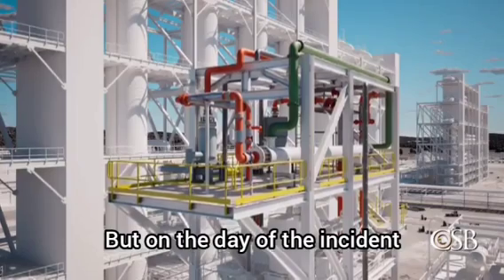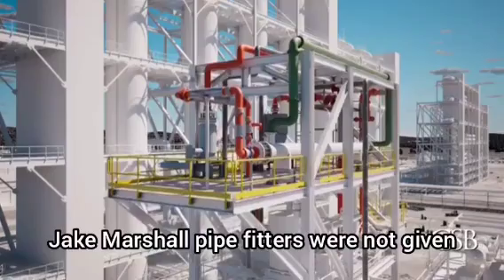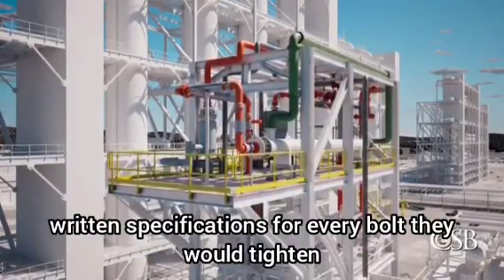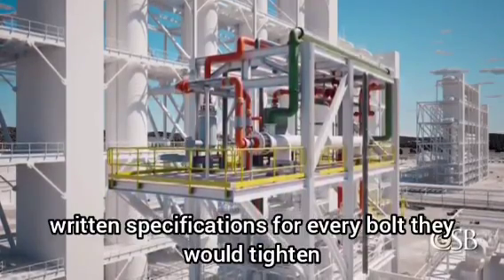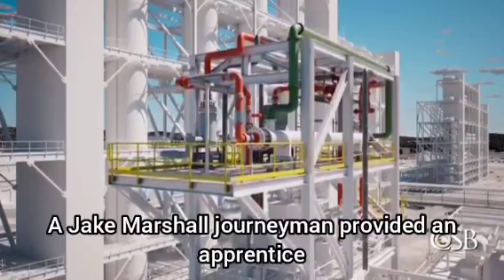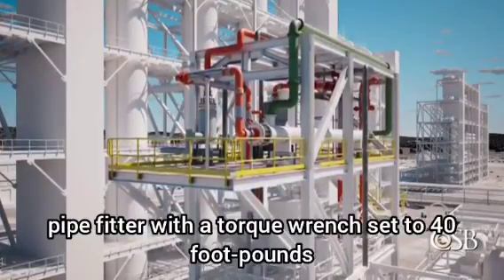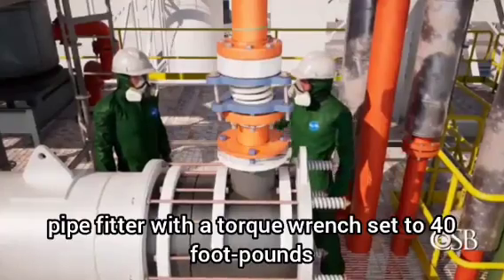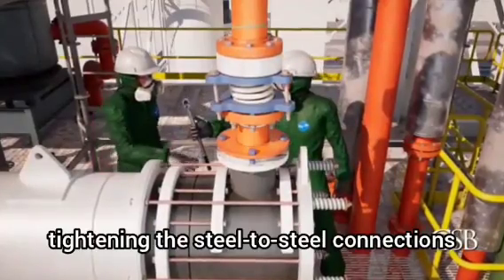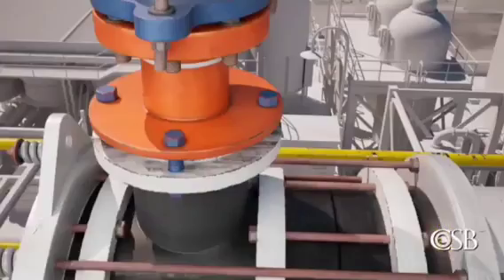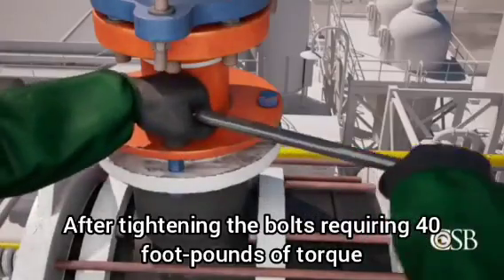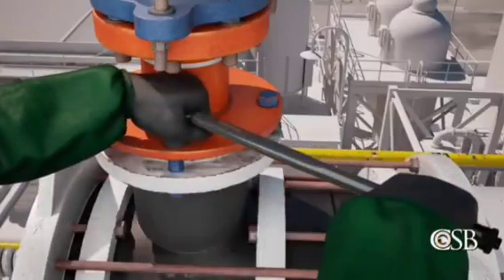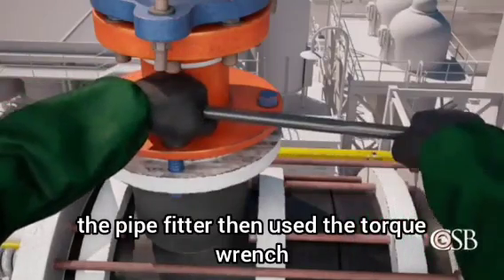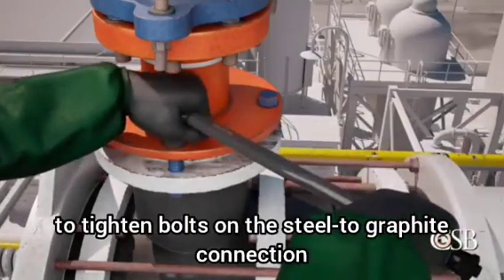But on the day of the incident, Jake Marshall pipe fitters were not given written specifications for every bolt they would tighten. A Jake Marshall journeyman provided an apprentice pipe fitter with a torque wrench set to 40 foot-pounds, which is the setting for tightening the steel-to-steel connections. After tightening the bolts requiring 40 foot-pounds of torque, the pipe fitter then used the torque wrench to tighten bolts on the steel to graphite connection.